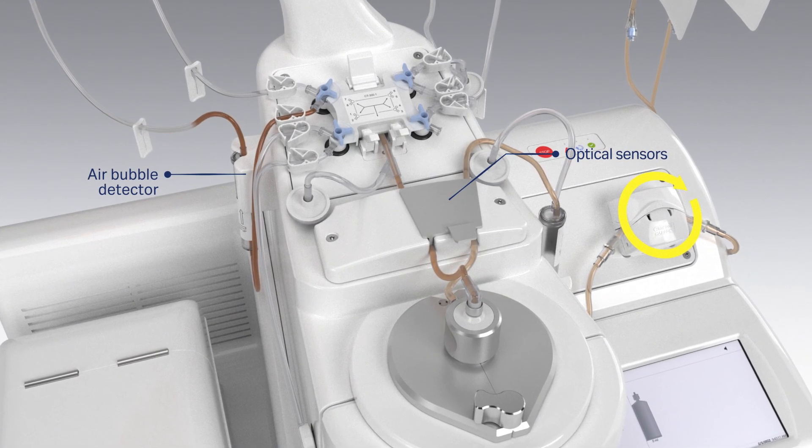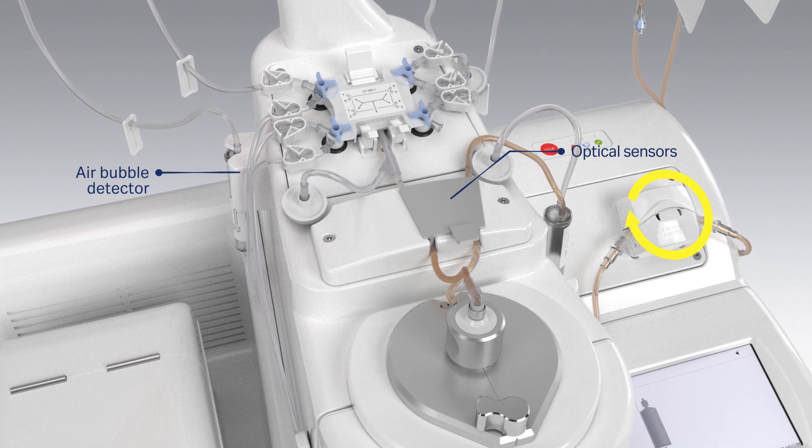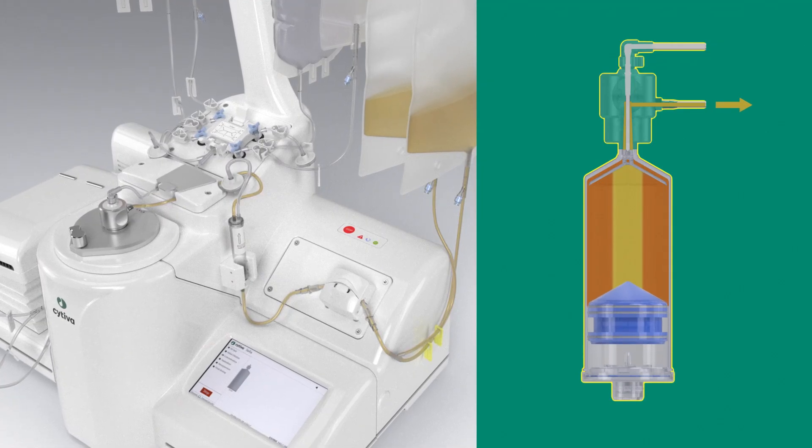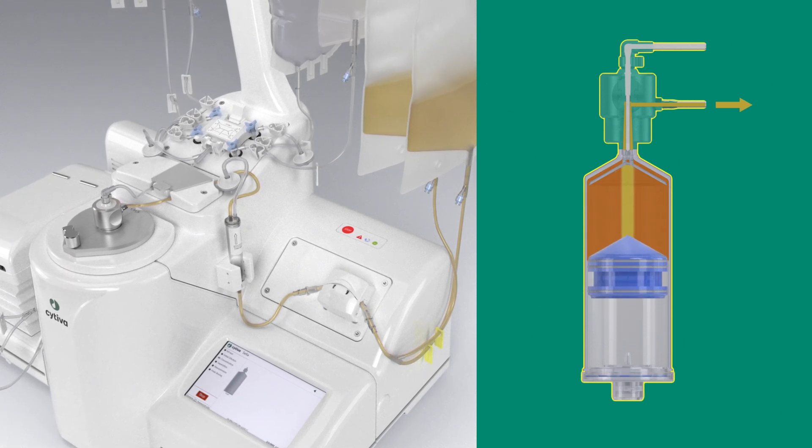Ultrasound and optical sensors detect when the initial bag is empty to secure the procedure. After processing the initial product, the remaining supernatant is removed via the piston motion.